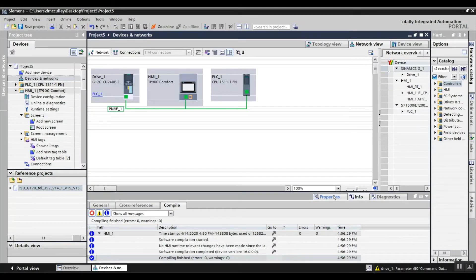This is Darren McCulley with Professional Control Corporation. Today I'm going to show you how to display your G120 drive faults on the Siemens HMI. The drive has to be firmware version 4.7 or above, and we're using TIA Portal version 13 Service Pack 1 or above for this application. There's a white paper on our website pccweb.com underneath the blog area that shows this application also.